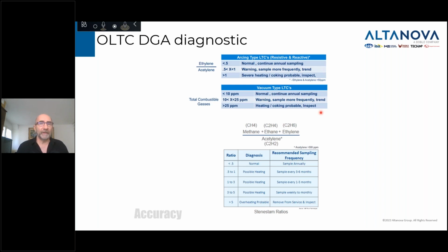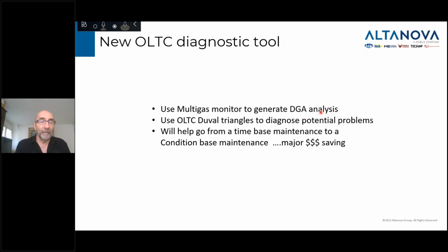At Doble, for the analysis, and I've heard the same thing for Reinhausen, they also have their own diagnostic tool for DGA. Why are people starting to do this? I think North America is doing it more in general than the rest of the world, but slowly it's getting there. We're starting to see it with customers in the Asia Pacific area, mostly because they want to go from time-based maintenance to condition-based maintenance. A lot of customers spend a lot of time every couple of years stopping their transformer, opening the OLTC, and checking if there's potentially any problem in it. Often they find there's none. They have to shut it down and put it back, but it costs a lot of money, labor, and downtime.